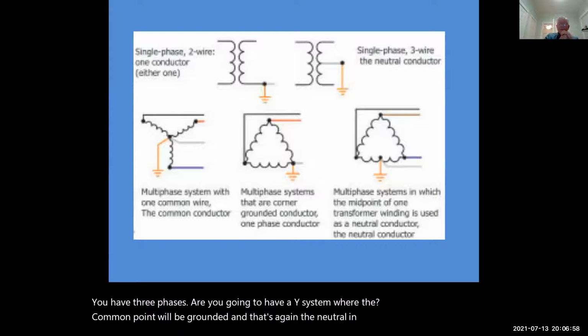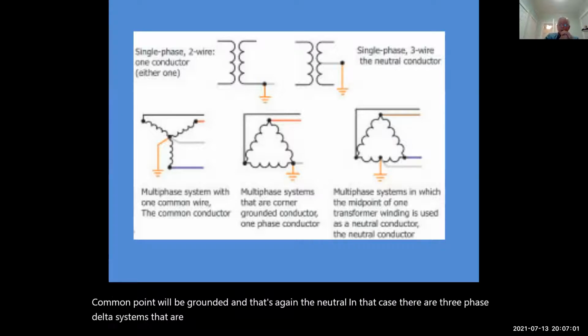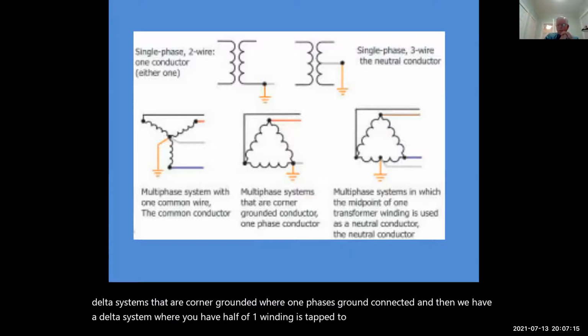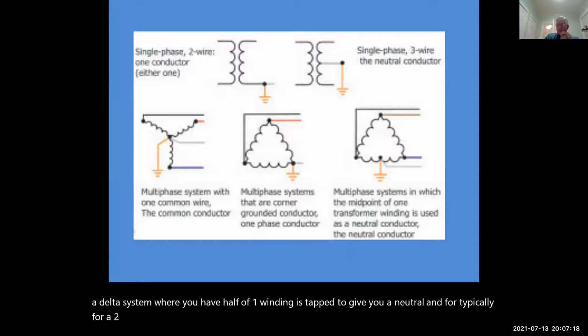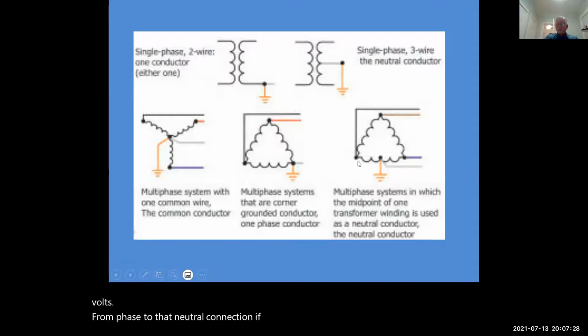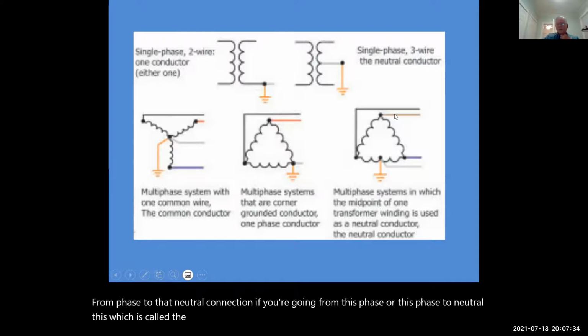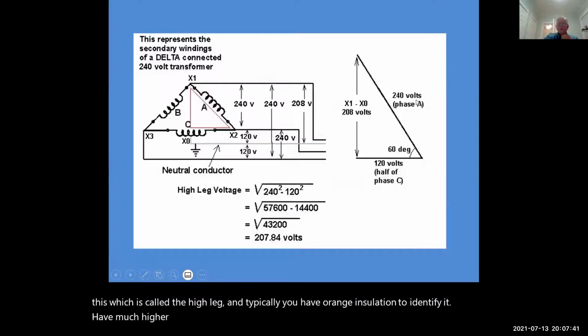In that case, there are 3-phase delta systems that are corner grounded, where one phase is ground connected, and then we have a delta system where half of one winding is tapped to give you a neutral. Typically for a 240 volt 3-phase system, this would give you 240 volts phase to phase and 120 volts from phase to that neutral connection, if you're going from this phase or this phase to neutral. This is called the high leg, and typically you'll have orange insulation to identify it. You'll have much higher voltage. You'll actually have the 208 volts.